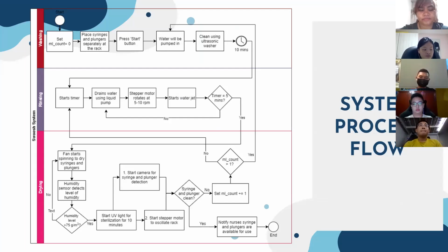It is split into 3 different phases, which are washing, rinsing, and drying. For the washing, there will be a variable called ml count, which I will explain later. This ml count will be set to 0. Afterwards, the syringe and plungers are separately placed on the rack by the nurses, and the start button will then be pressed. Upon that, the water will be pumped in, and it will be cleaned by the ultrasonic washer for about 10 minutes. Afterwards, the rinsing phase comes in, which starts the timer, and then the water will be drained using the liquid pump. The stepper motor rotates at 5 to 10 revolutions per minute, and the water jet starts. These 3 functions repeat concurrently for 5 minutes.